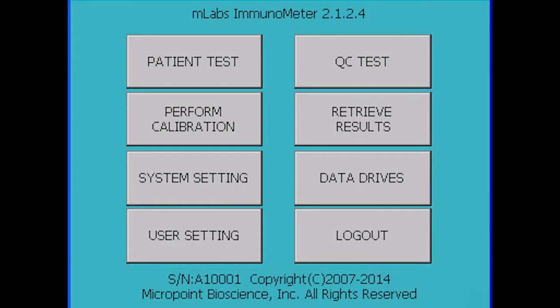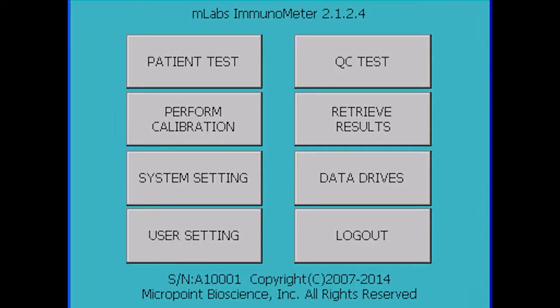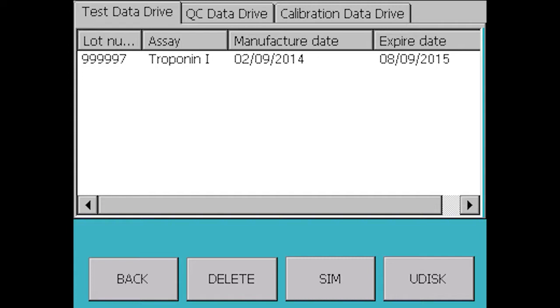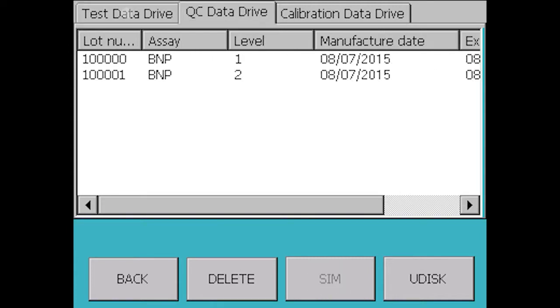To use a USB disk, tap Data Drives followed by U-Disk. For a SIM card, tap Data Drives, SIM. Select Test Data Drive or QC Data Drive according to the data drive type to be installed. There is no need to install calibration data drives unless the user has lost the calibration cartridge. Touch SIM or U-Disk. The data drive will be installed automatically.